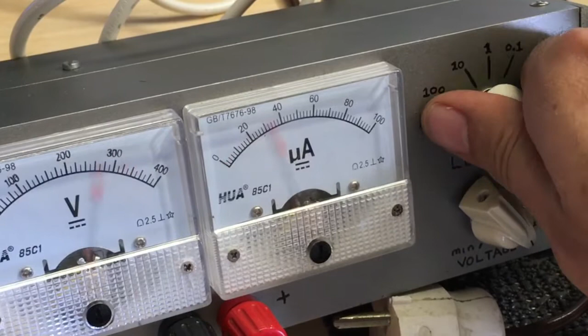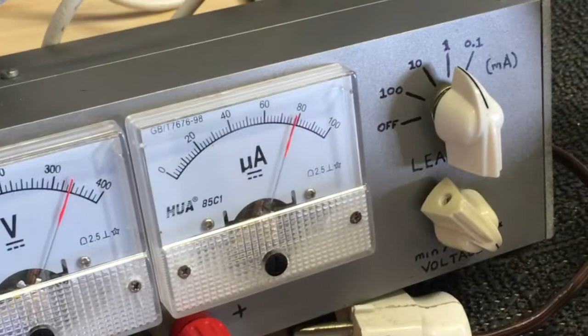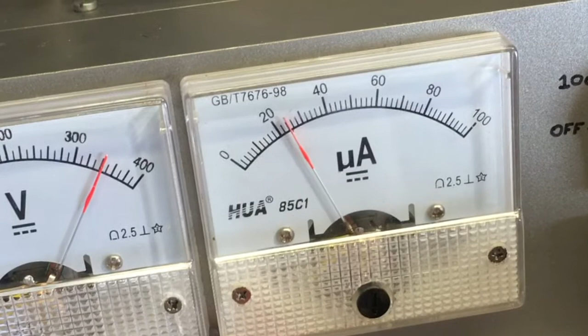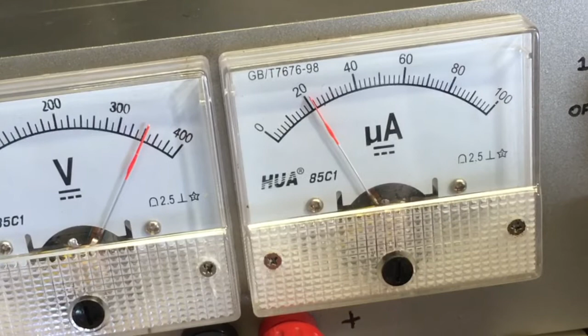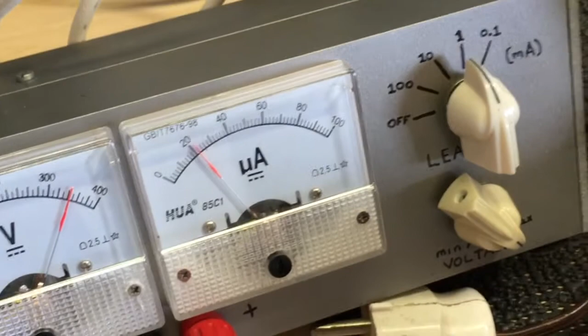Let me just put that on and see if we can get an example. It's at high voltage, so it should do that. Now, that's the 1 milliamp range, and it very quickly drops - that's 300 microamps, coming down to 200 and something microamps, 0.2 milliamps. It settles between 100 and 200 microamps, which is a lot lower than the 2 milliamps that I found it at.